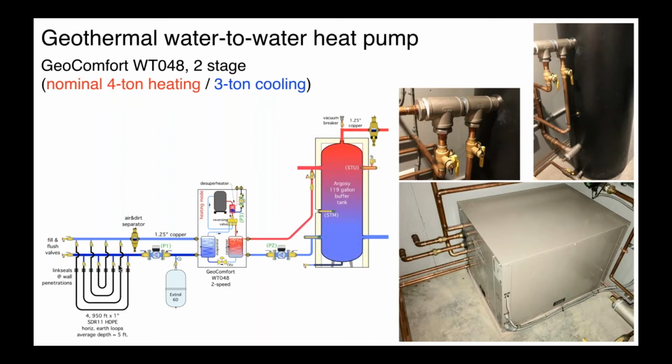I forget the exact volume. I want to say somewhere in the range of maybe 150 gallons. So we're putting quite a bit of antifreeze in there at 25%, and with toxic or flammable materials, just handling the alcohols in a mechanical room, I just don't feel comfortable with it. So, there is no ideal antifreeze. They all have pros and cons, but we went with the propylene glycol on this.